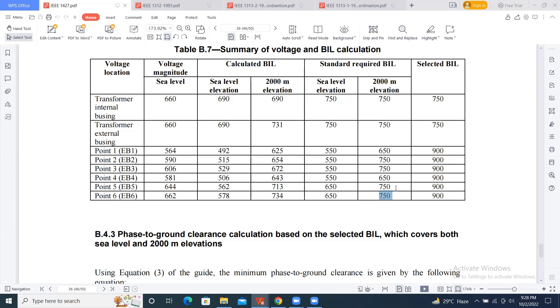So, based on this, I can again achieve this 750 or less than 1050, which is the highest BIL level in the 220 kV system. So, they have done these exercises and they found that optimum points to place the lightning arrester is entry of the substation, outside of the substation, on either side of the transformers. That is the reason why they choose those locations for the lightning arrester.